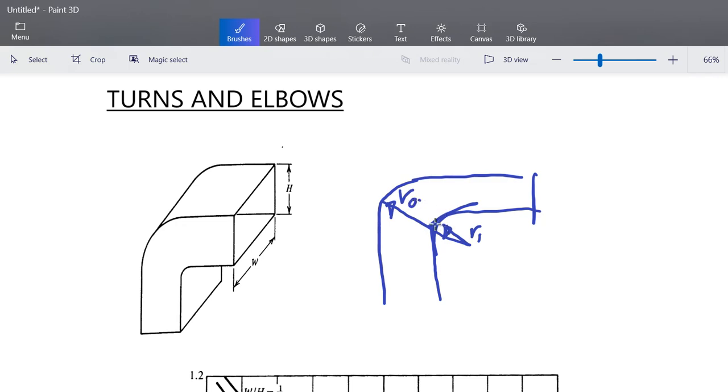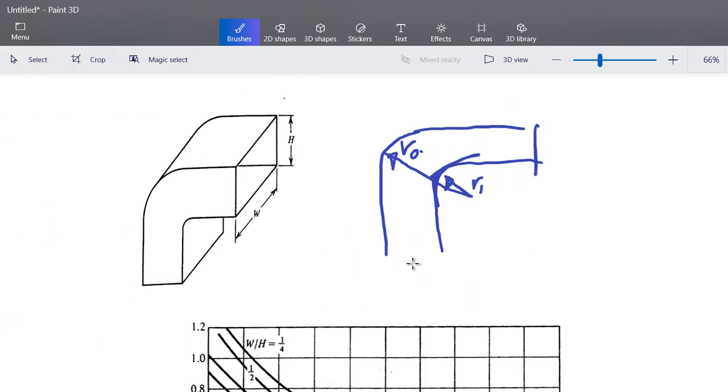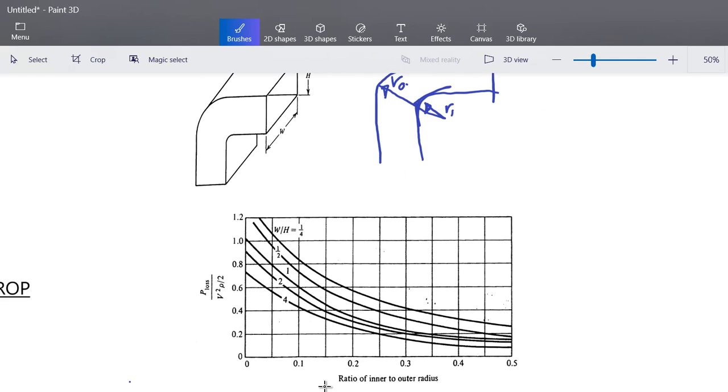Okay. So yung sinasabi niya, if you're going to draw your duct, you can compute that one. So how much radius you're going to give. This one is the ratio of the inner, so that will be R1 divided by your RO, outer. So yeah, makukuha naman yan by means of the dimension. So if you get the value of R1 or RO, plot it here. So we have the decimal places, R1 and R2, so it will be decimal places also. So if you get the value, for example, if you get 0.2 the ratio, then you have the ratio of your width and height of the duct.